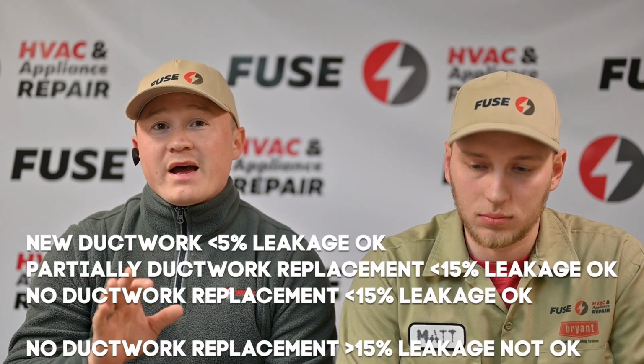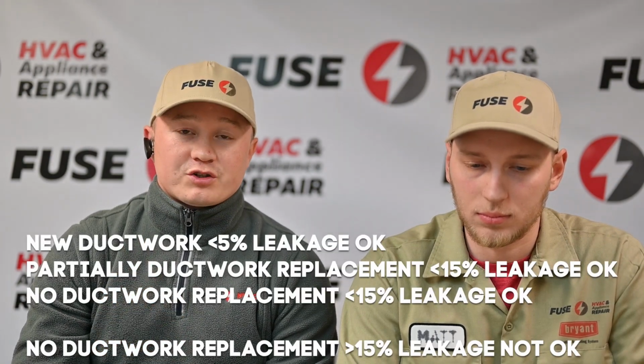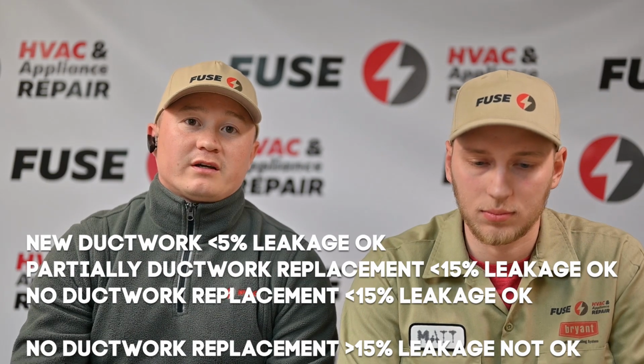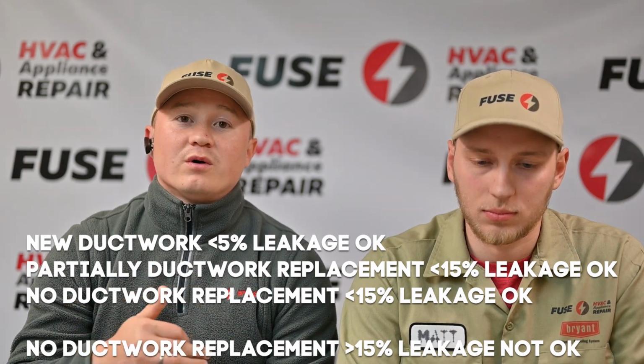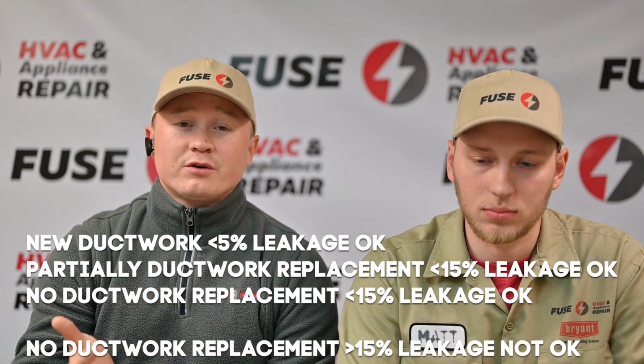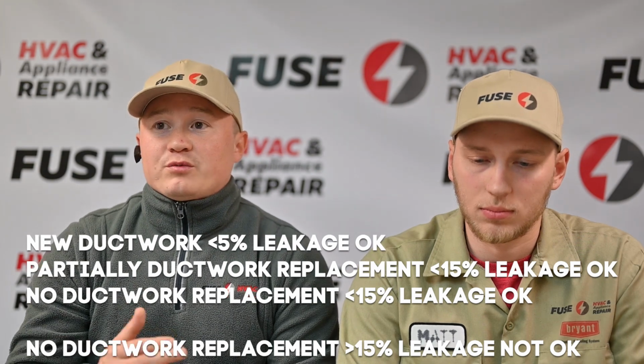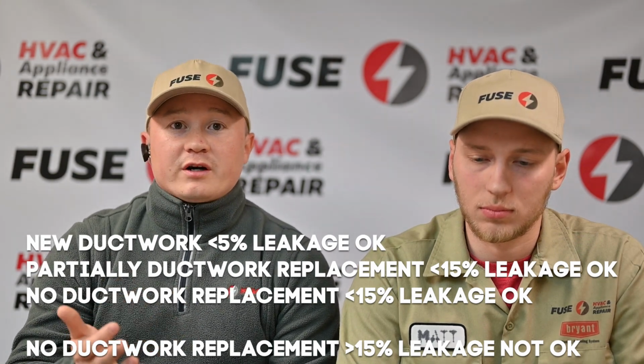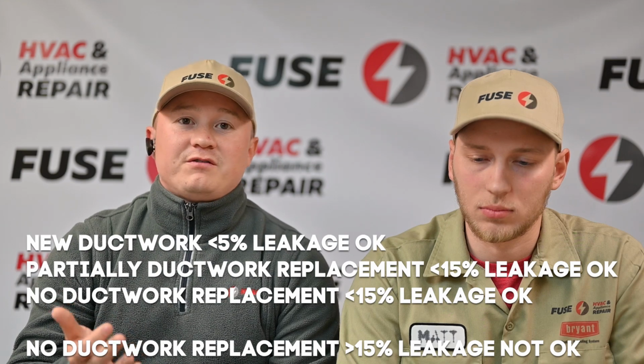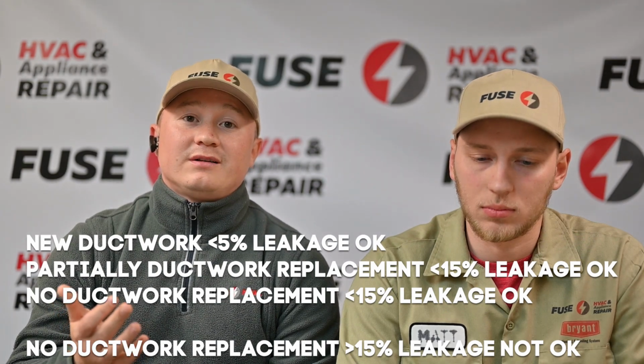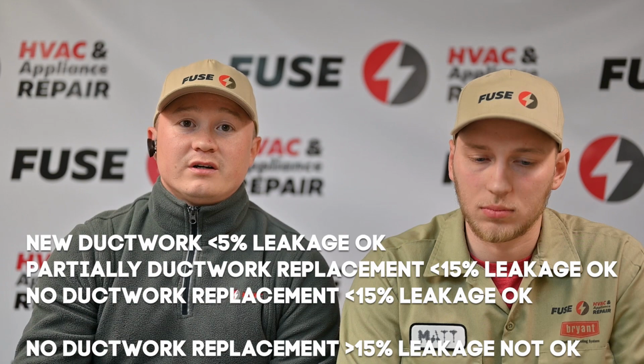It's actually the home energy rating system, like HERS. If we do new ductwork installation, we're supposed to have maximum 5% leakage. If we've only done an AC installation or furnace replacement, we're supposed to provide all ductwork at least within 15% leakage of the existing ductwork.